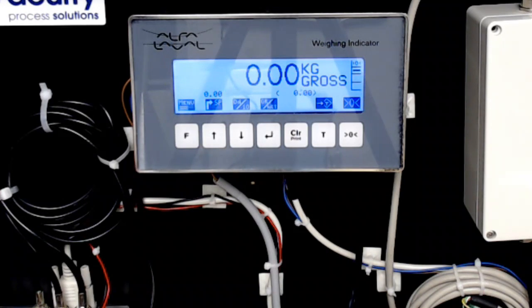We're going to approach today's session as if I had just built a system, put the load cells on it, and had the empty vessel sitting on top, which is pretty typical. If you think about it, when you're weighing something, if I build a skid, put my load cells on it, and set a tank on it, it's going to read the weight of the tank. So first I have to take the tank weight out of the equation so we can then measure what's important to us, which is likely the volume in the tank.